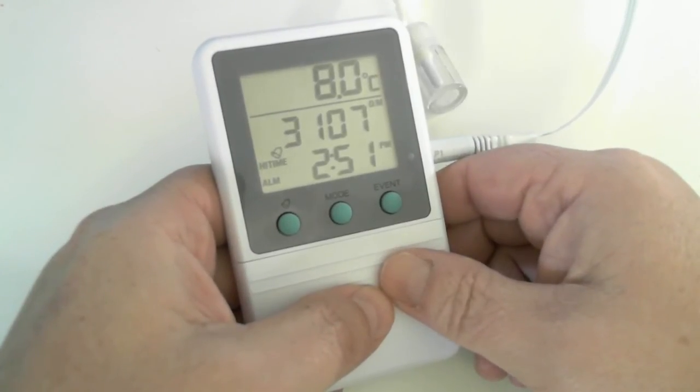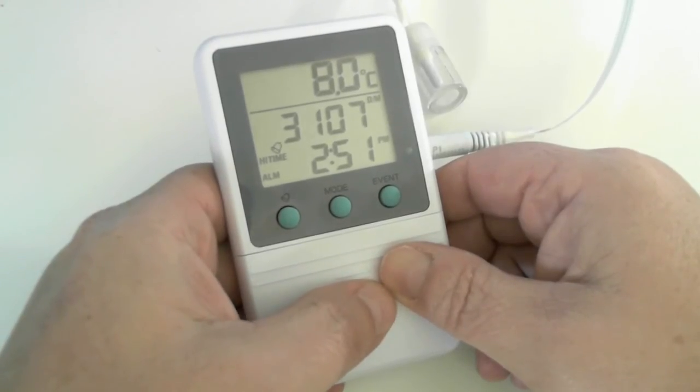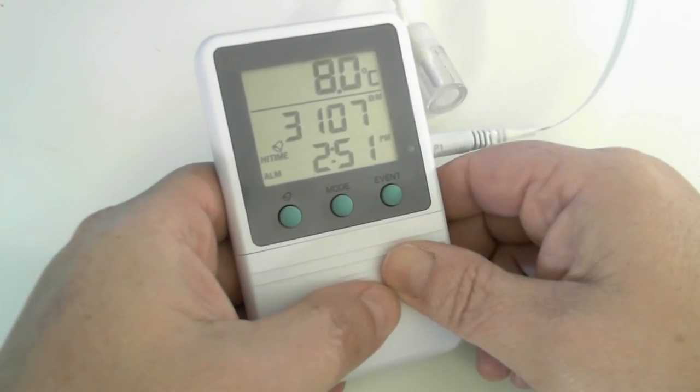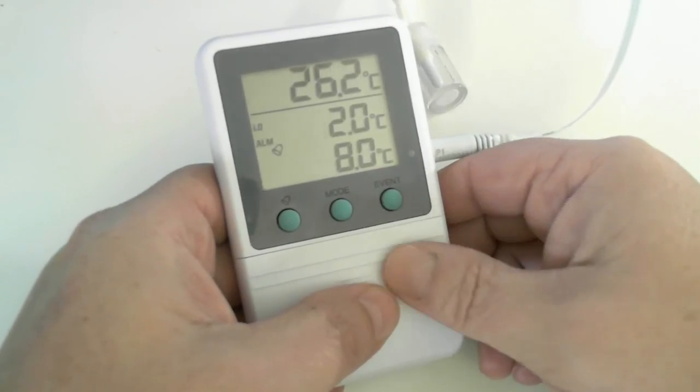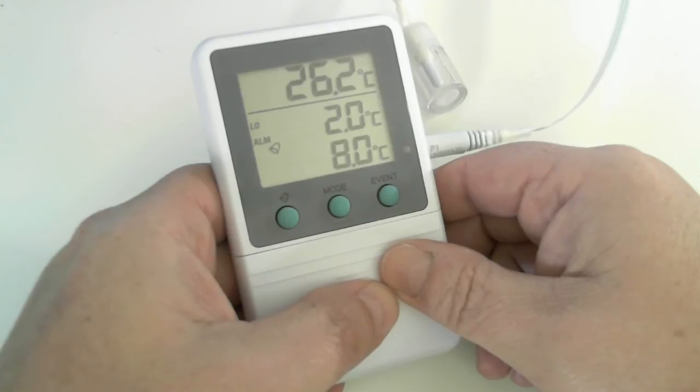If you hit event, our low alarm had no conditions, so nothing is recorded. Hit event again. But our high alarm that is set at 8 degrees C was passed at the month of July 31st at 2:51 PM. And you hit event again. You come back to the main alarm setting screen.